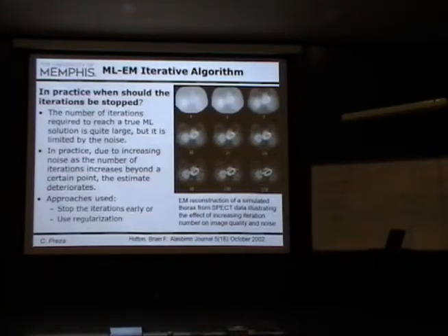that is based on simulated SPECT data, which is single photon emission computed tomography of a simulated thorax. In the first iteration, what you have as a solution is really blurred, and as you increase the iterations, 10, 15, things start to look really nice, or more resolved and clear. But then as the iterations of this algorithm progress, it gets noisy, or what they call salt and pepper appearance. So this is very characteristic of all EM algorithms, that your result will deteriorate.